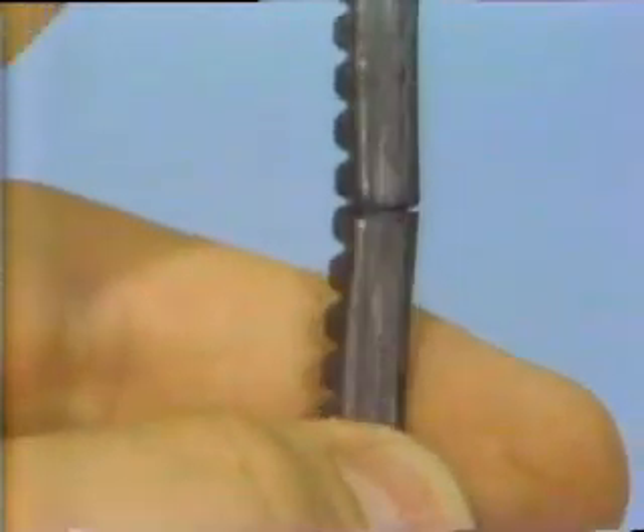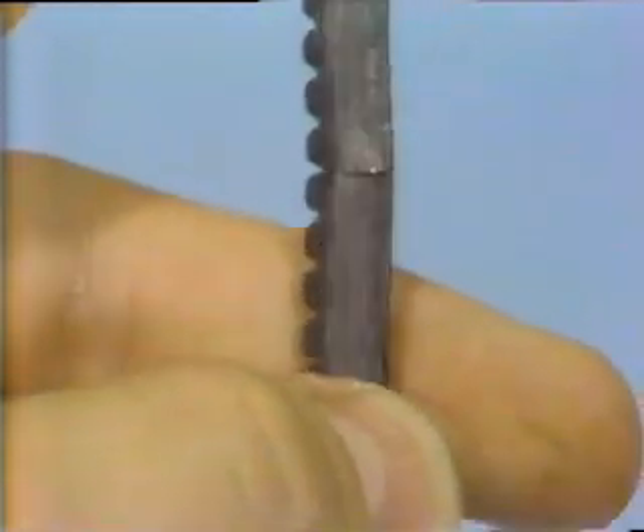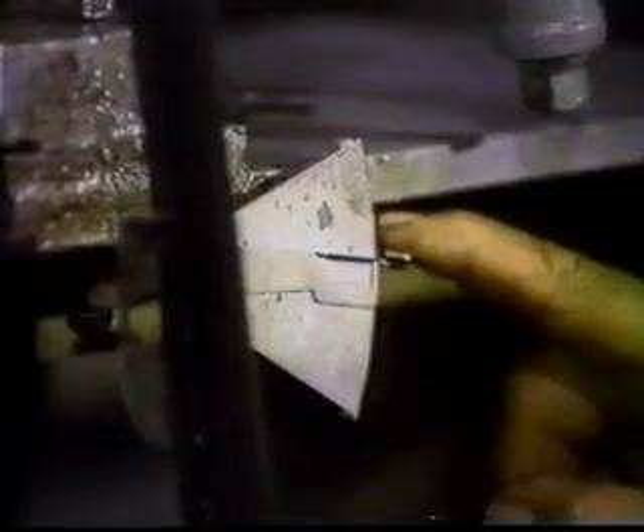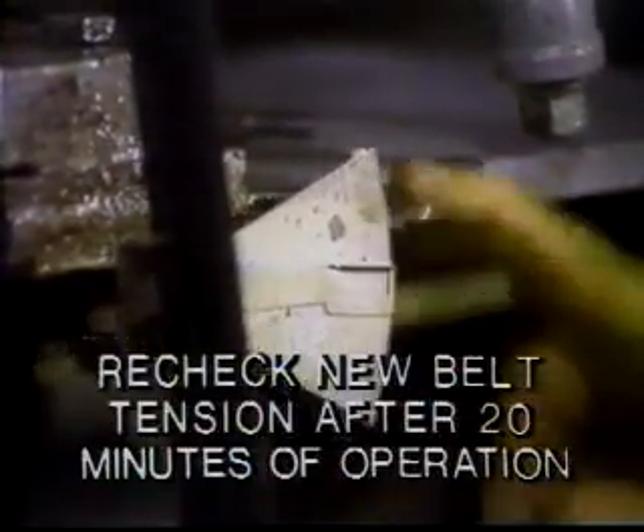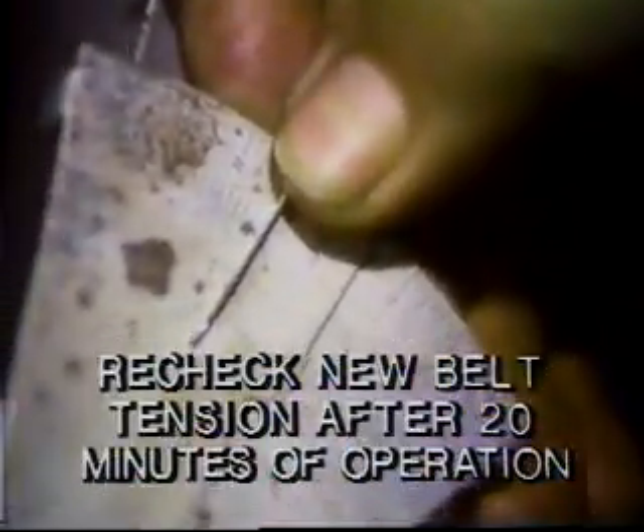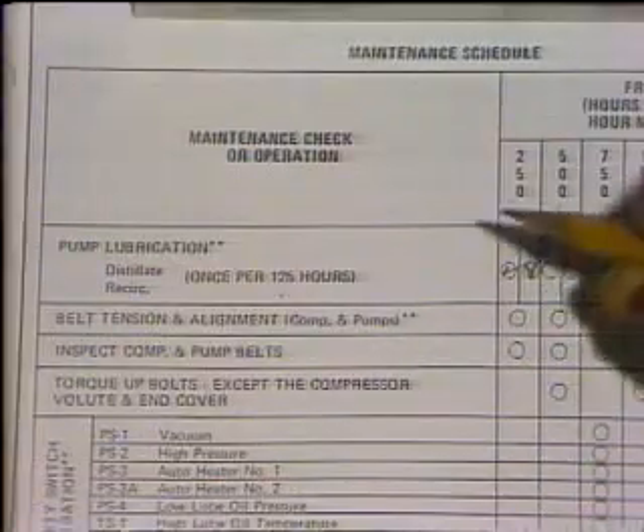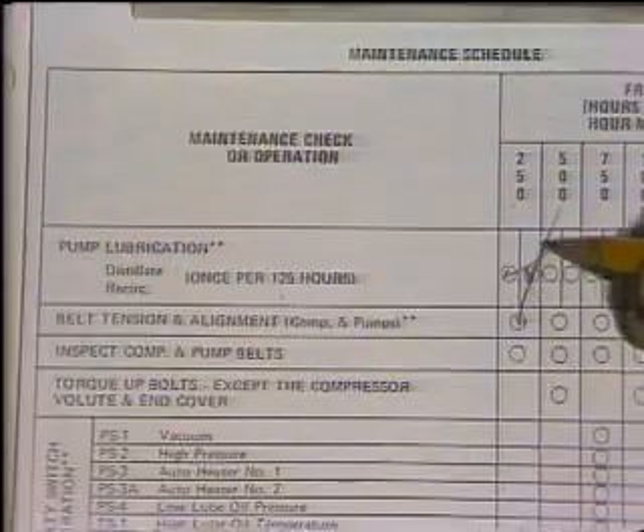And be sure to check the belts for cracks and signs of wear every day. If you have to replace them, check the tension again after about 15 to 20 minutes of operation, once they've had a chance to seat properly, and replace them only with matched sets of belts. On our newer water makers, a type of multi-section power band has been provided. This band is an improvement over the old separate belt system. Any new belts you purchase will be this type and will fit your existing pulleys. Now, check these items off on your schedule sheet as you complete them.